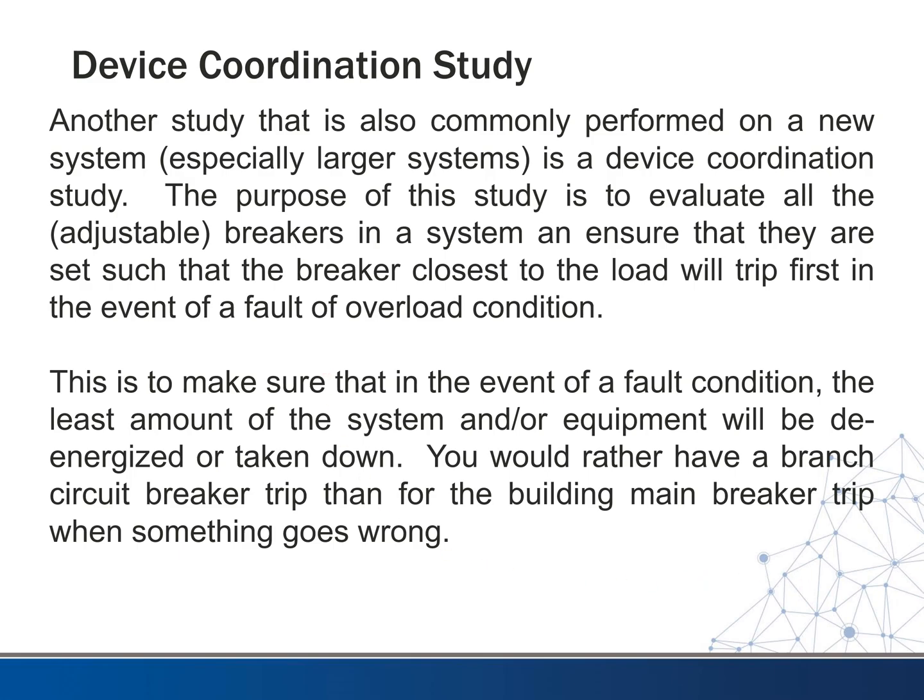This ensures that in the event of a fault condition, the least amount of the system and equipment will be de-energized. You would rather have a branch circuit trip closer to your fault than have the main breaker trip every time and take your whole facility down. So the purpose of this study is to make sure that the breaker closest to the fault trips first.